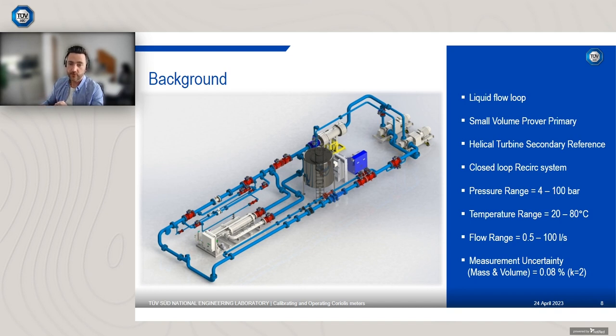Then the fluid flows through the prover, through one of three helical turbine master meters, which you can see to the left of the prover. They are the white devices, 3 different line sizes. So depending on the flow rate, we flow through one of those master meters. It flows round, and then we have two separate test sections depending on the meter size. So we have a nominal 6-inch line for our larger meters, in the region of between 4-inch and upwards, and then we have a 3-inch test section for meters 3-inch and smaller. This allows us to accommodate the meters and also achieve the required flow rates for that meter size. In terms of our operating conditions, we can operate from 4 to 100 bar.